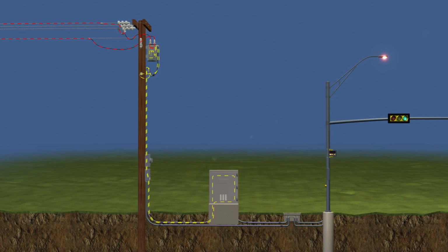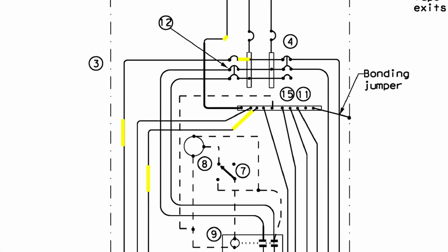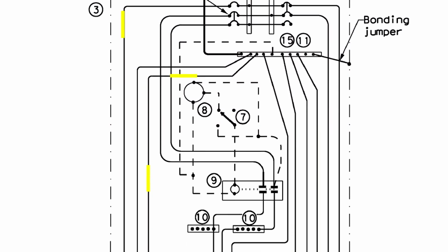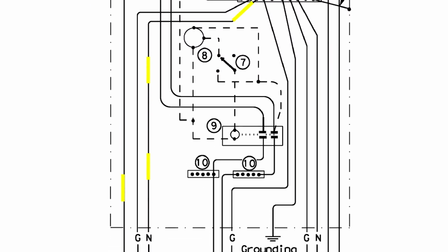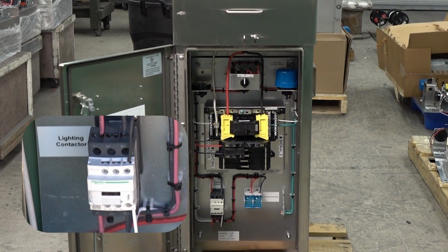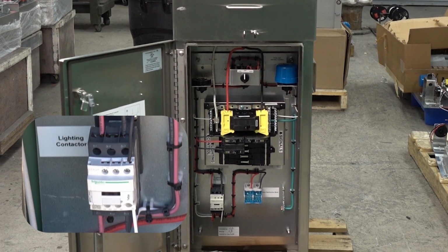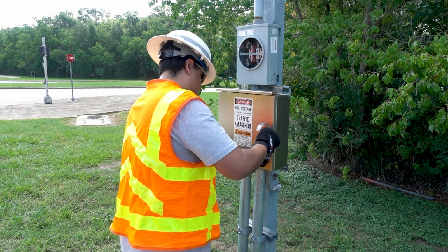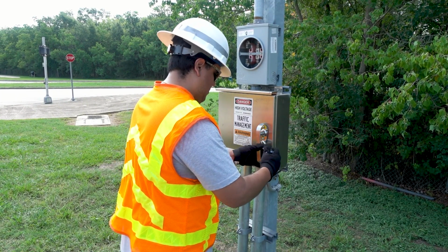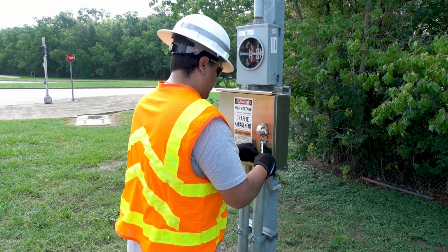Other electrical loads, such as traffic signals, have power passed to them by branch circuit breakers that bypass the lighting contactor. These circuits do not pass through the lighting contactor and remain energized as long as their breaker is turned on. These electrical parts are placed inside the enclosure. To restrict unauthorized people from touching these energized components, a lock is placed on the enclosure door.